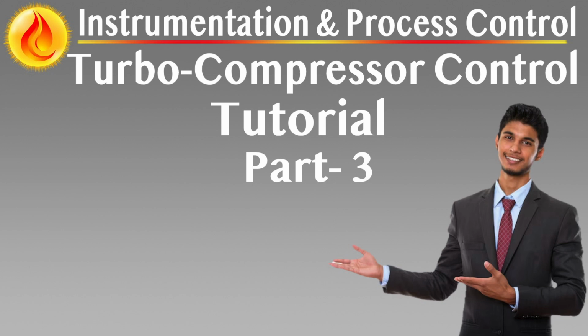Core capabilities of the machine protection system. Continuous real-time monitoring. The MPS constantly assesses vibration, displacement, thrust position, and temperature signals across critical components such as compressor bearings and casings, gearboxes, power and gas turbines. System-level integration. Protection logic is embedded within the TCCS but executed independently of process control functions to maintain response speed and functional integrity.